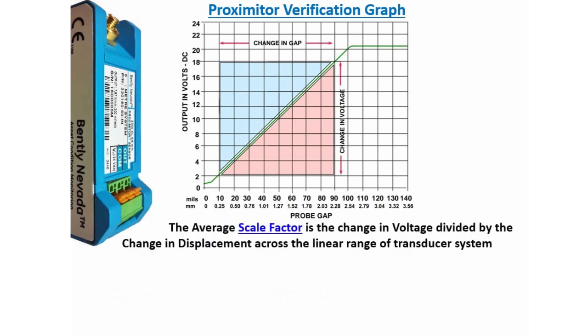Therefore, for a proximity displacement system, the average scale factor is the change in voltage divided by the change in displacement across the linear range of transducer system. The linear range of 8 mm Proximitor system is 0.254 millimeters to 2.286 millimeters.